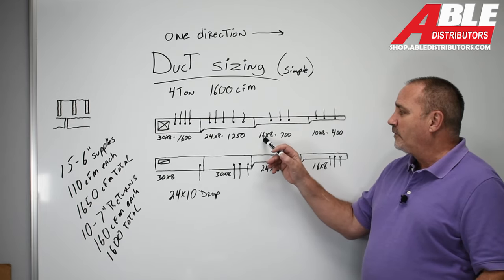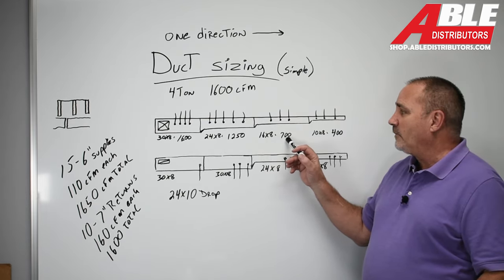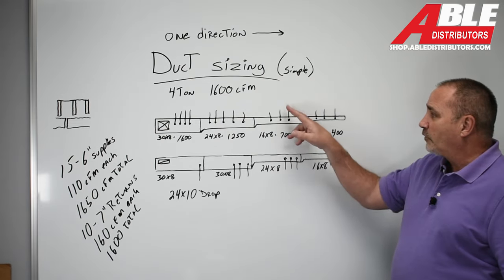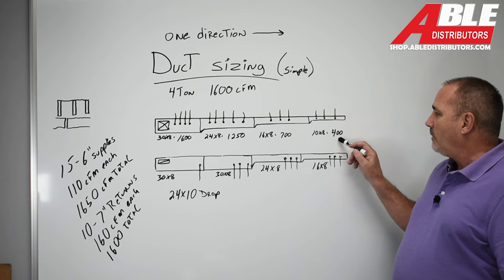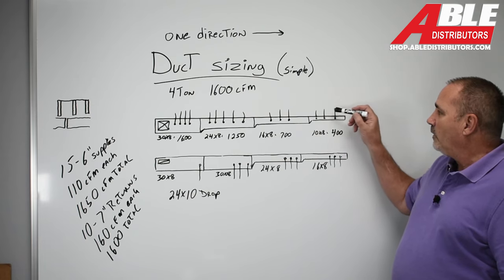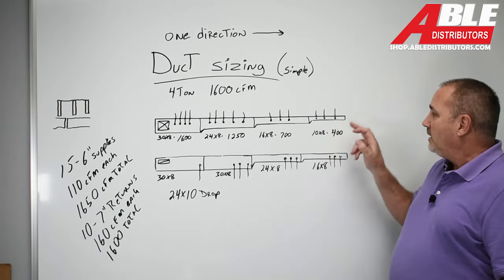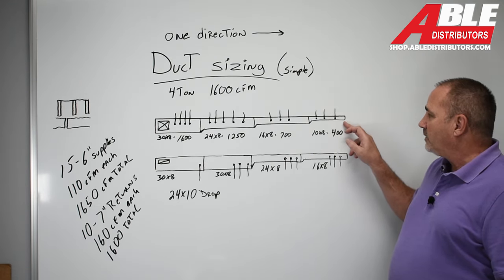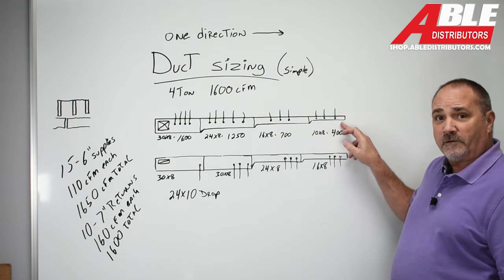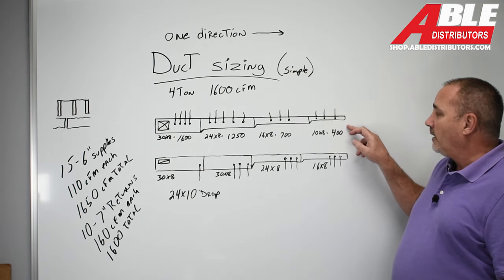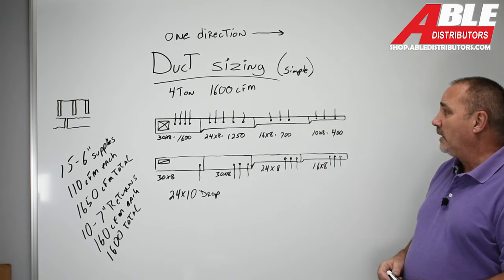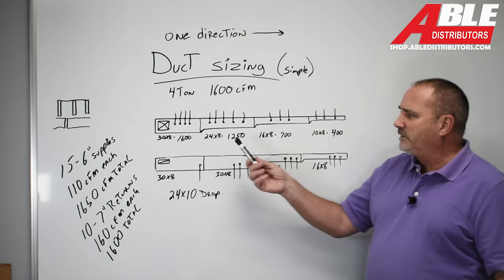We've marked down to 16 by 8, which is capable of 700 CFM. We took three more supplies off of that. We stepped down to 10 by 8, which is capable of 400 CFM. We only have three supplies coming. You never take one off the end cap. You should never be within a foot of the end cap if you can avoid it. Even if you had to take it off the side and step it out, it's the right way to go rather than taking off the end cap.